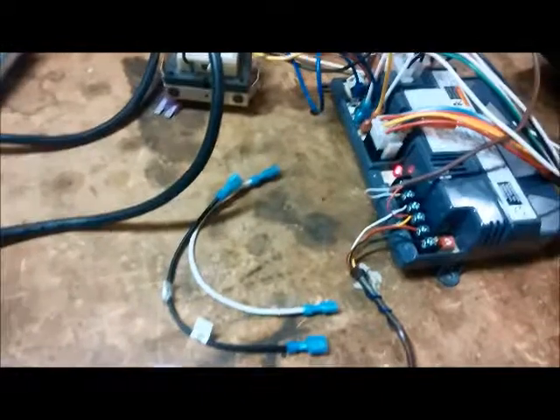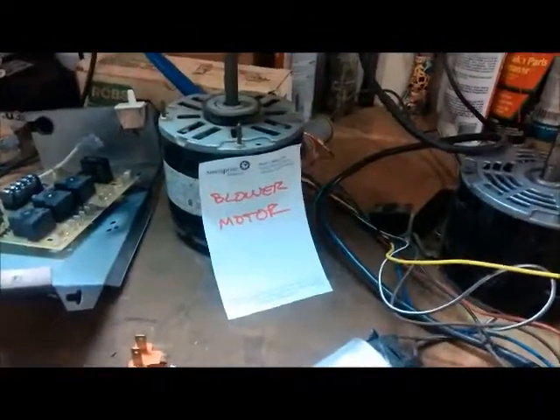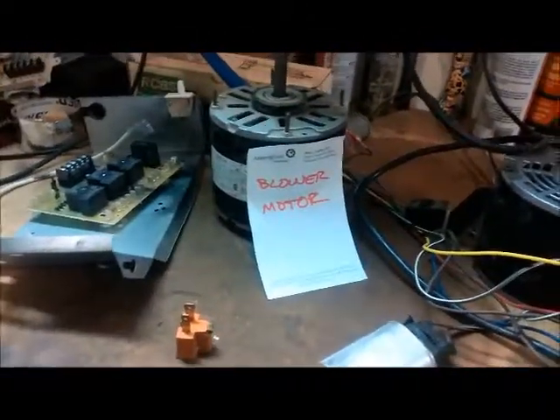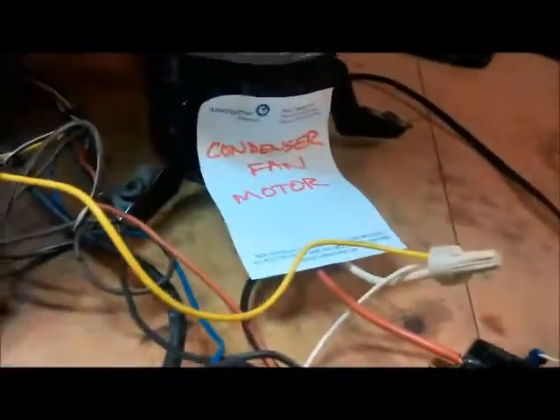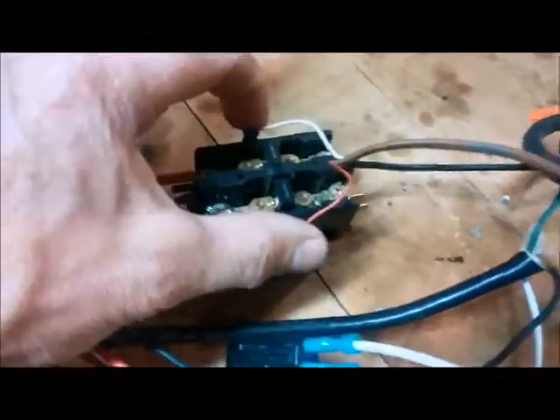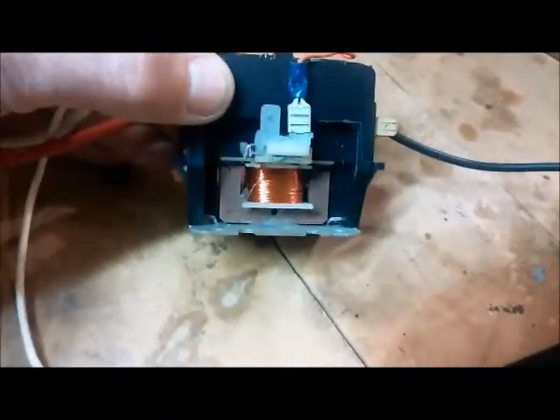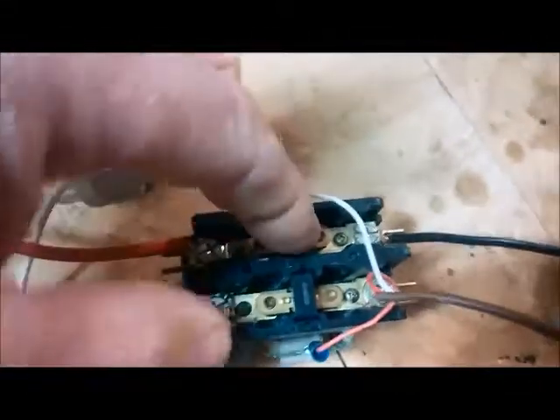Air conditioning. Let's turn on a call for cool. When a call for cool is initiated, simultaneously our blower motor will come on, unless there's a delay, it'll maybe come on a minute or two later. And our condenser fan motor should start, as well as our compressor. So simultaneously, when we put 24 volts across this coil, that coil, when it's energized, is going to magnetize and pull in our high voltage, which I just did manually.